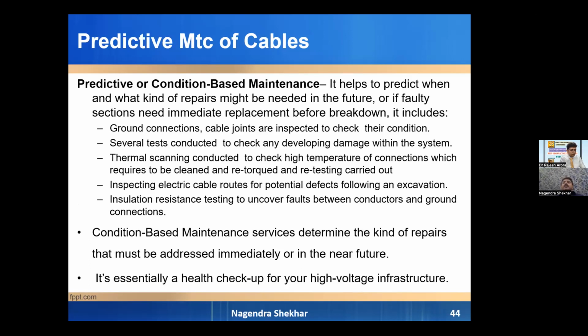Predictive and condition based maintenance. Here we have to conduct two tests. One is the IR test, to see how much leakage current there is. Second is thermal scanning. We also conduct tan delta tests for cables to ensure the working and condition, the health of the cable. So these are the predictive or condition based maintenance.